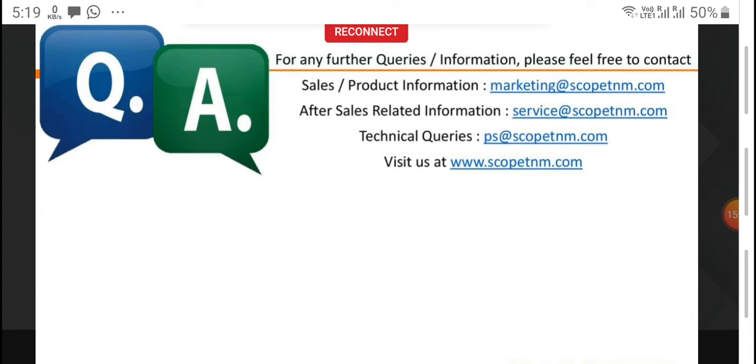Now, also Mr. Azaz Zikani has asked in the impedance method how the pinpointing can be done. So instead of answering that, you can tell us how much accuracy we can get in the impedance method, roughly, and how much best accuracy we can get in our TWFL system. Okay, sir. In the online traveling wave system, the guaranteed accuracy at best is 150 meters plus minus. That means almost 1 tower span.